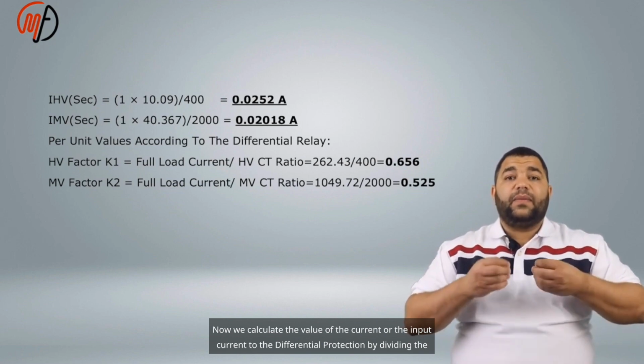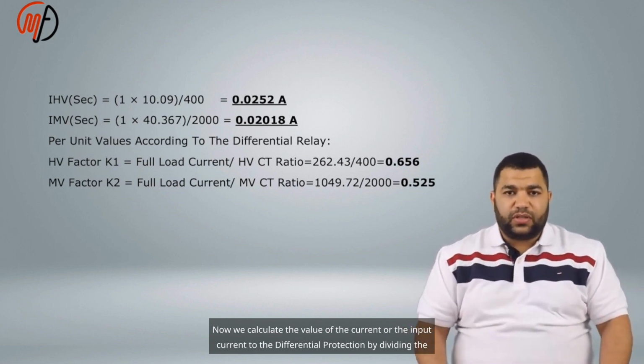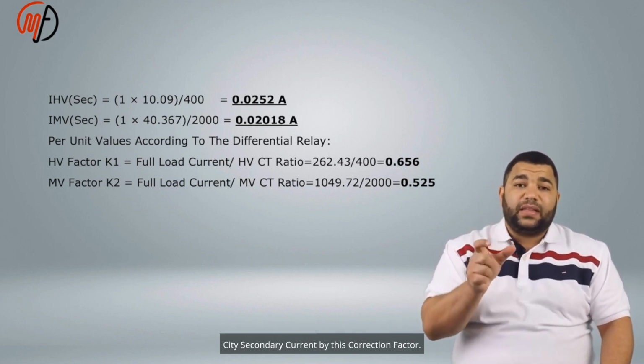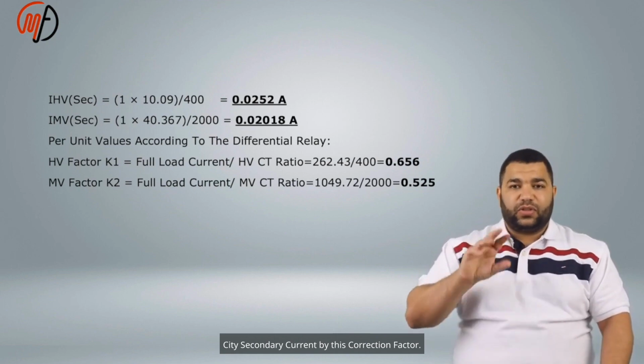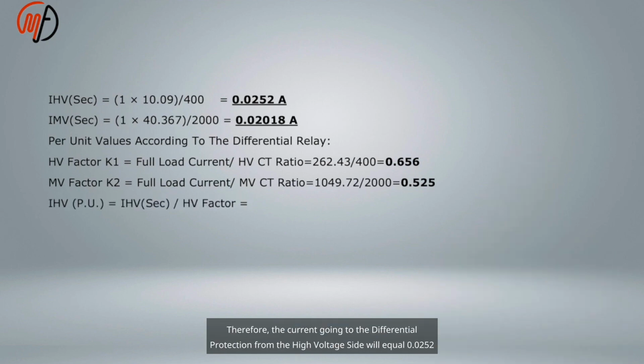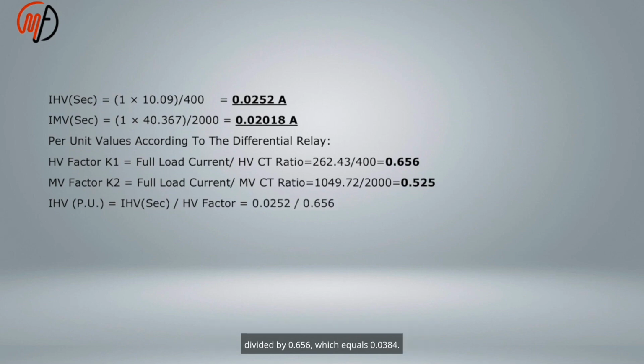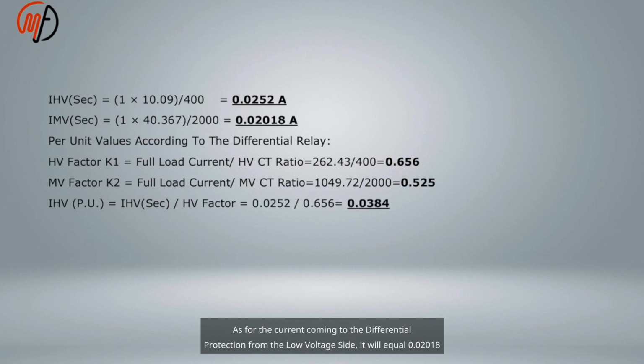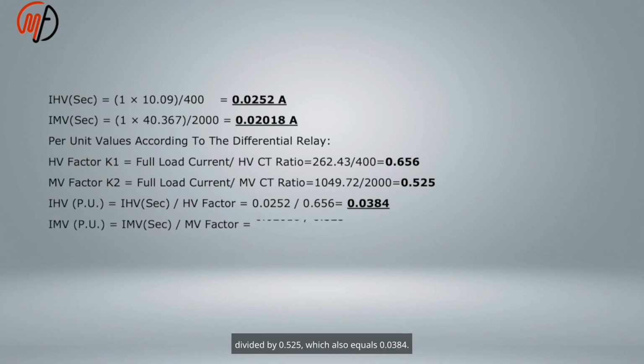Now we calculate the value of the input current to the differential protection by dividing the CT secondary current by this correction factor. Therefore, the current going to the differential protection from the high voltage side will equal 0.0252 divided by 0.656, which equals 0.0384. As for the current coming to the differential protection from the low voltage side, it will equal 0.02018 divided by 0.525, which also equals 0.0384.